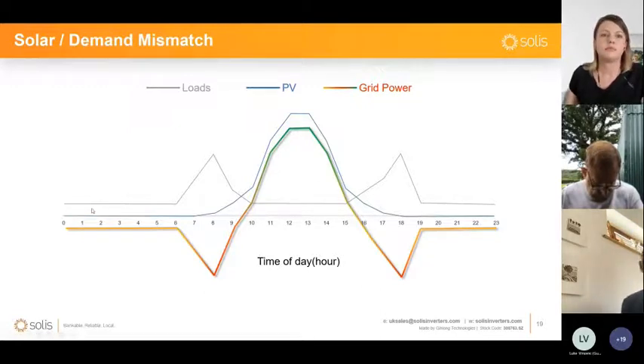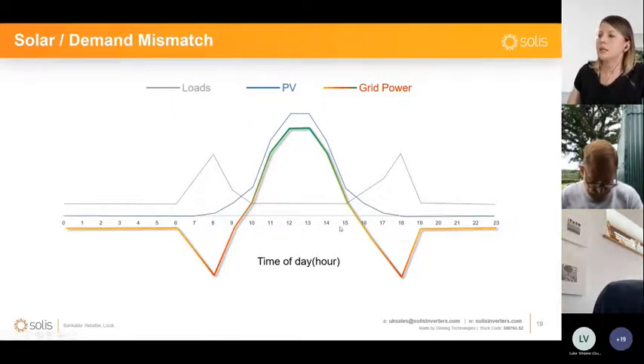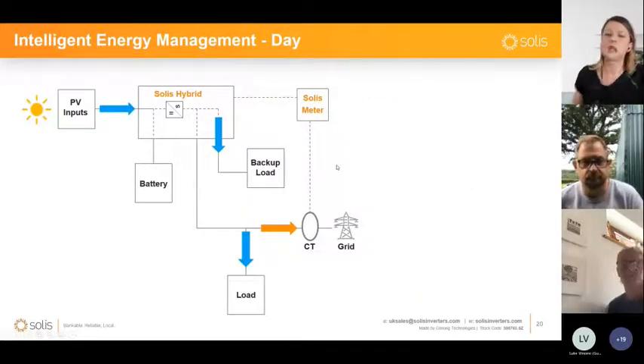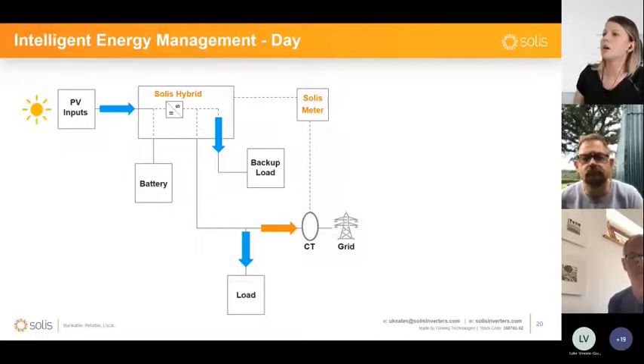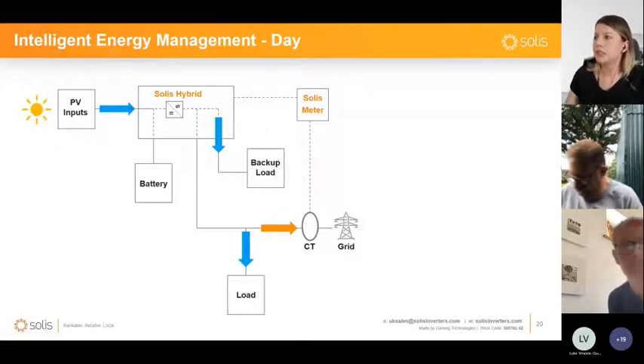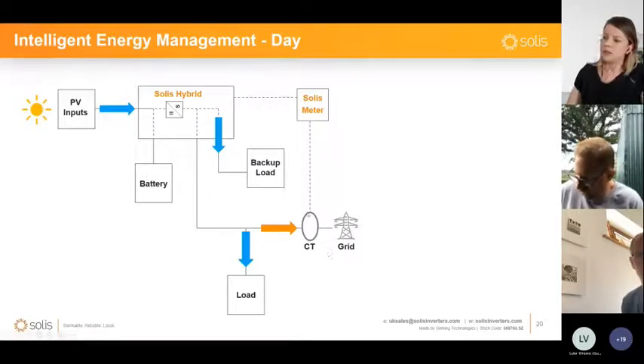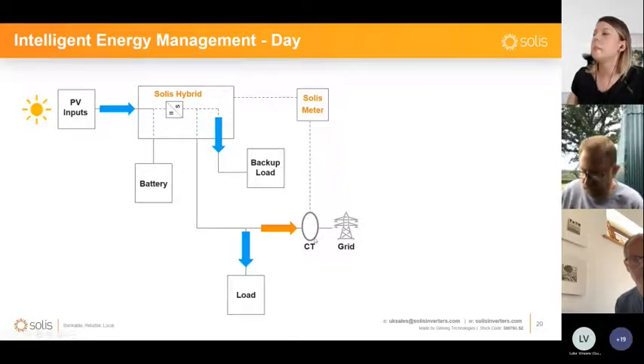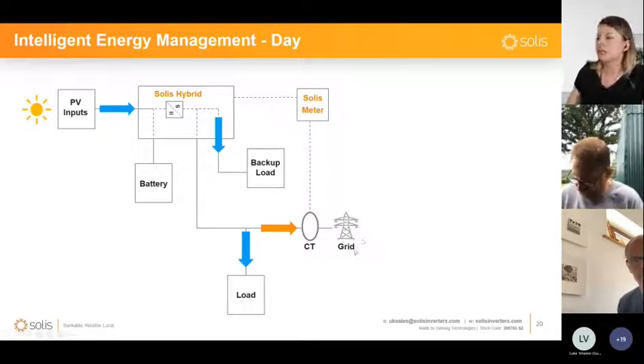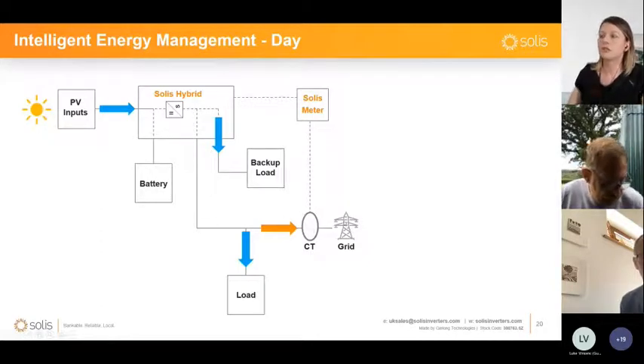As always, during high peak consumption times, you can also get higher tariffs. So normally during the day, how this should look like: the PV is generating energy from the PV input. That energy is either consumed locally or it's being exported into the grid. The Solis meter, which should always be installed on the main AC connection point, needs to constantly monitor that export and import of energy coming in from the grid. Actually, during the day, you're going to almost always have an export if the sun is shining.